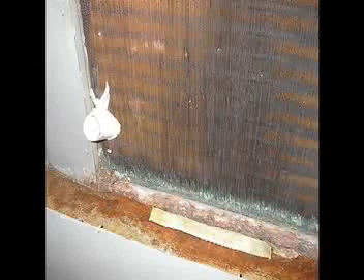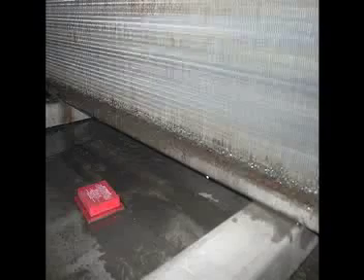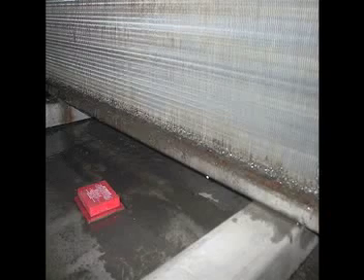First thing people do when the air does not appear to be cool enough is turn down the thermostat. Regardless of how low it is dialed, the air is not going to get any cooler because the efficiency in the coils is lost. All turning down the thermostat does is increase energy output, whereas keeping coils clean allows for peak performance and maximum energy conservation.